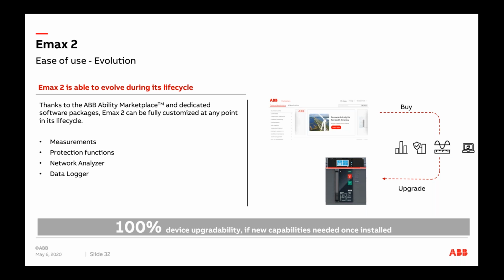So the Ekip Touch trip unit, like you saw in one of my slides, is upgradable with all functionality all the way up to a Ekip Hi-Touch trip unit, which means the measurements, protection functions, or analysis on the network, logging data, all that can be upgraded through software. Now we have various versions of doing that software upgrade. It can be either specified from the factory side and be installed or enabled from factory.